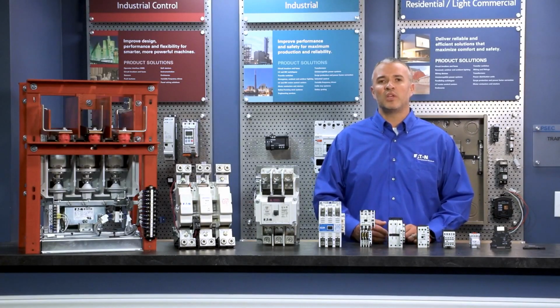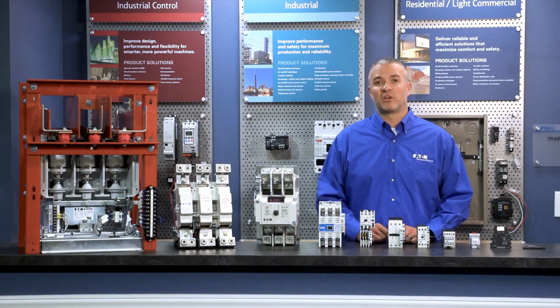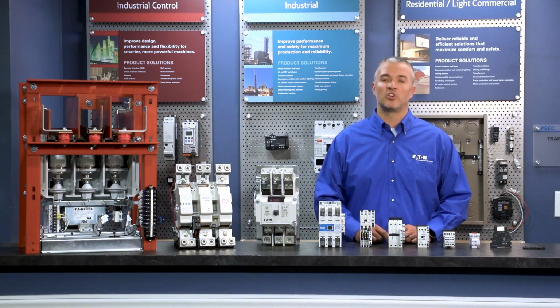The smaller contactor usually means it is less expensive, but remember, more front-end engineering is required when this is done, and there are more discrete sizes compared to NEMA. While NEMA standards list 10 sizes of contactors to operate motors from 2 horsepower to 900 horsepower, IEC standards have 20 sizes to cover the same range of motors. This is why there has historically been a misconception that IEC contactors are smaller and less expensive than NEMA. IEC starters are typically not designed to be serviced. Instead, they are replaced after a failure. NEMA devices are generally serviceable without removal of the starter from its enclosure or bucket.